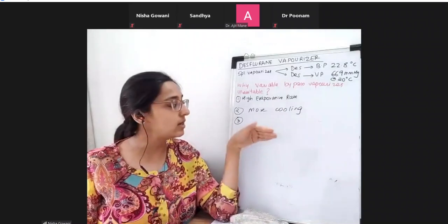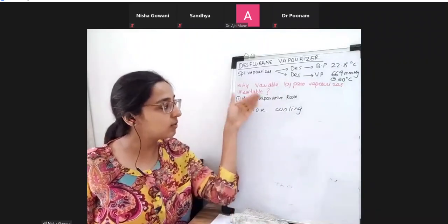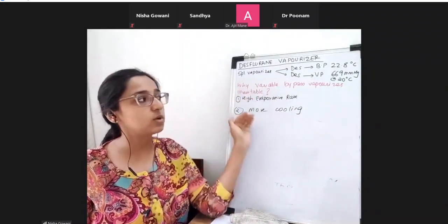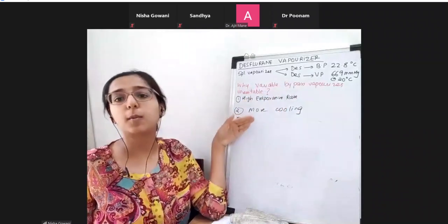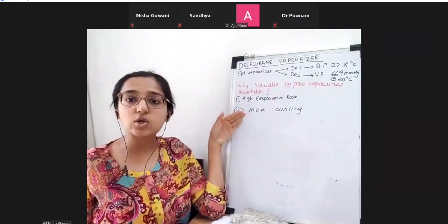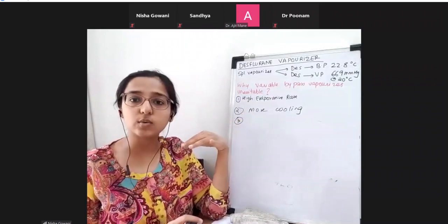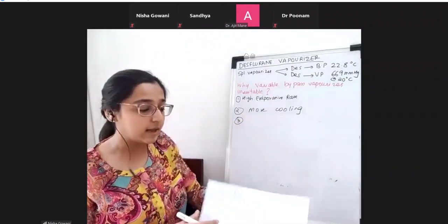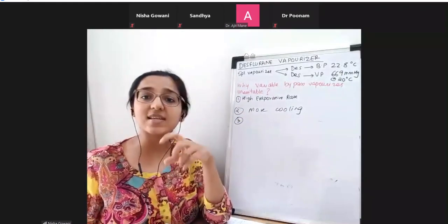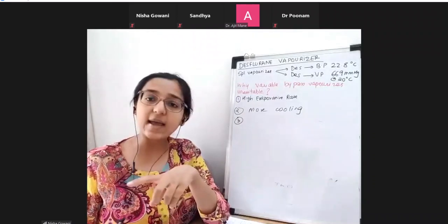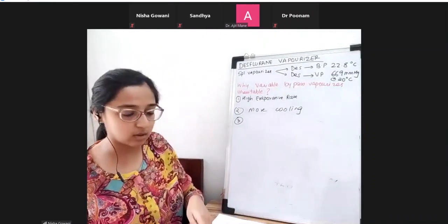All right. So these are the problems which we want to overcome, because if we use a variable bypass vaporizer, these are the problems that we will face. Correct. So that is why we need to use a different vaporizer. And this vaporizer is known as Tec 6, okay, and Tec 6 Plus. So there are two vaporizers.